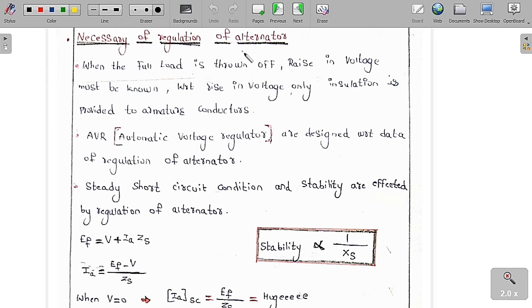Because these are some of the important points which give you the necessity of finding out the regulation of the alternator. Whenever the full load is thrown off, if you keep a full load, then the voltage across the load is minimum. Suddenly the load is thrown off, meaning open circuit. Then definitely the rise in voltage must be known. With respect to the rise in voltage, insulation is provided to the armature conductors.